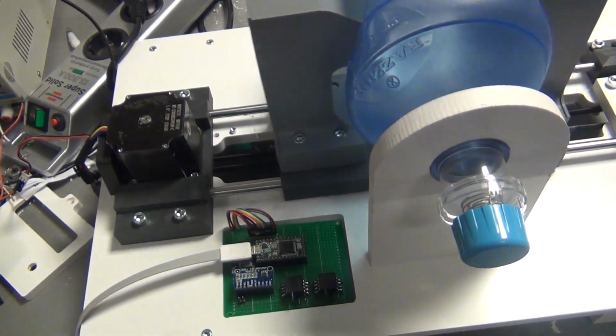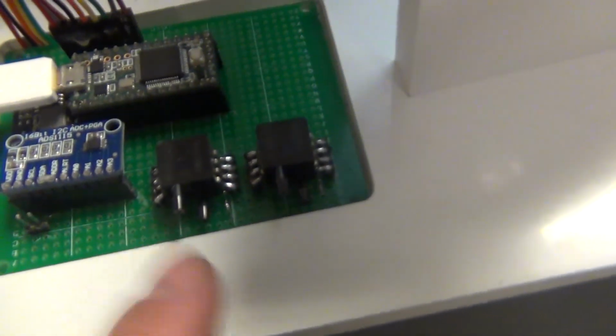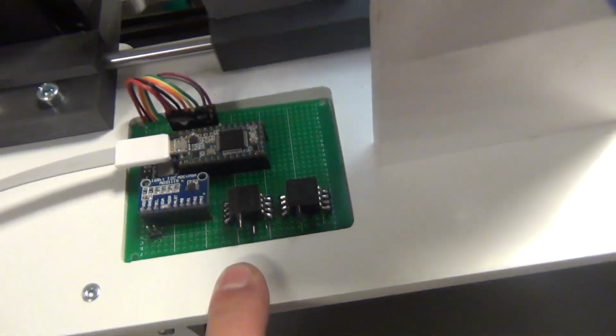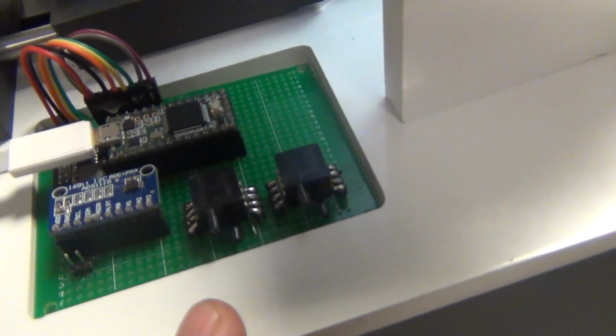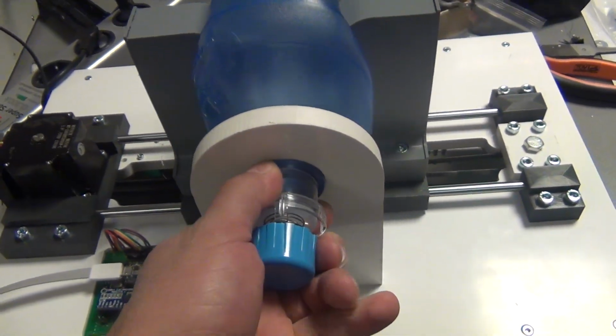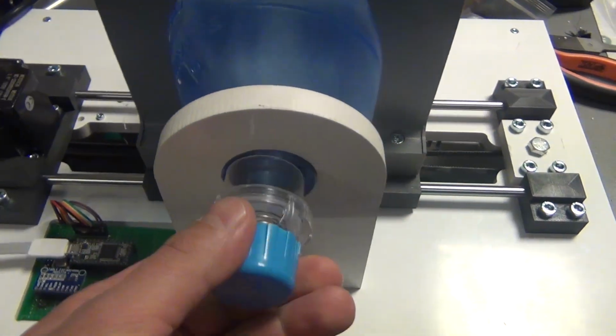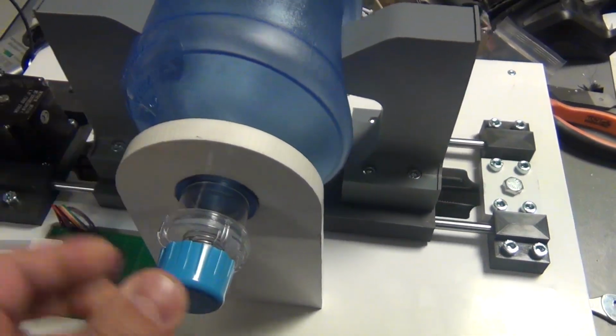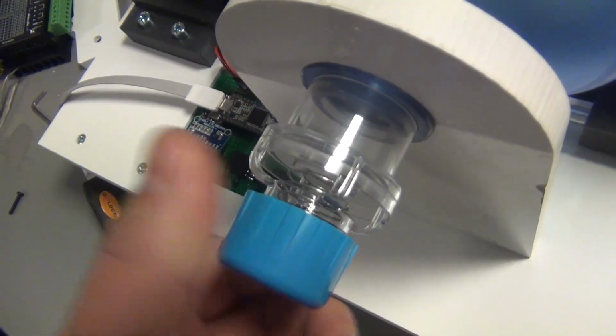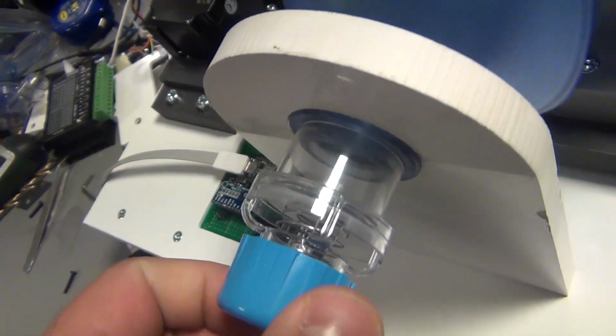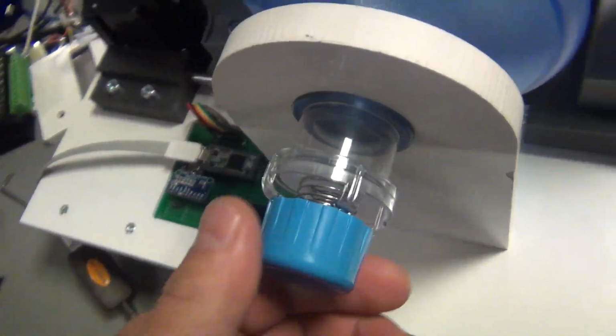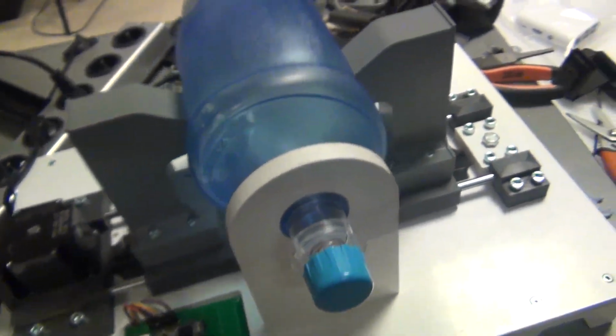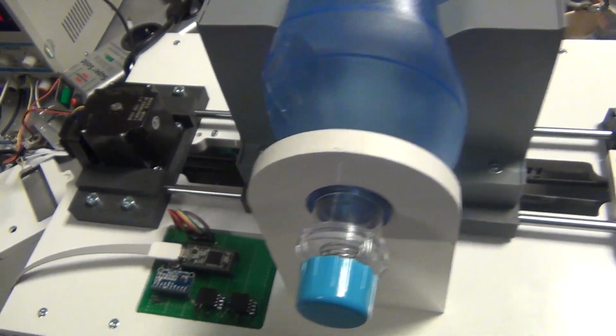So additionally to the board, we also added the pressure sensors. Those will be connected to the output of the... so I'm using this PEEP valve to test that it can push the pressure. It has a maximum of 20 centimeter setting here, but I think it's going to be around 30 at this point, and it's pushing fine.